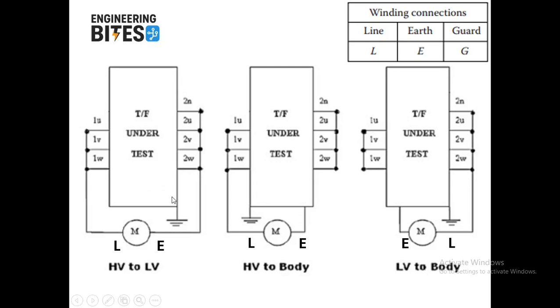In the first type, we are going to connect the short-circuited high voltage side to the L point of the megohmmeter, and we are going to connect the short-circuited low voltage side to the E point of the megohmmeter, and we are going to measure the insulation resistance for 1 minute. In the second test, we are going to connect the short-circuited high voltage side to the L point of the megohmmeter and the E point to the transformer's body, which is grounded to the earth. And in the third test, we are going to connect the short-circuited low voltage side to the L point of the megohmmeter, and we are going to connect the E point to the transformer's body or tank, which is grounded to the earth.